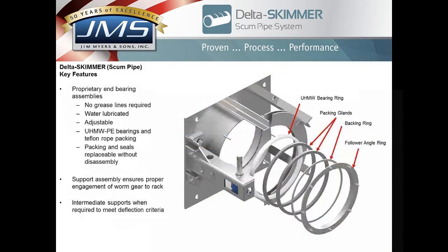Oh, but I did want to mention, these systems are water lubricated. No grease is required for these assemblies, importantly. And something that people don't pick up on, and I share with engineers, is that we as a manufacturer gain credibility with engineers when we're working through the specs. Some engineers say, I want grease anyway. Okay, but you need to use a food-grade grease. You do not want to use a petroleum-grade grease.